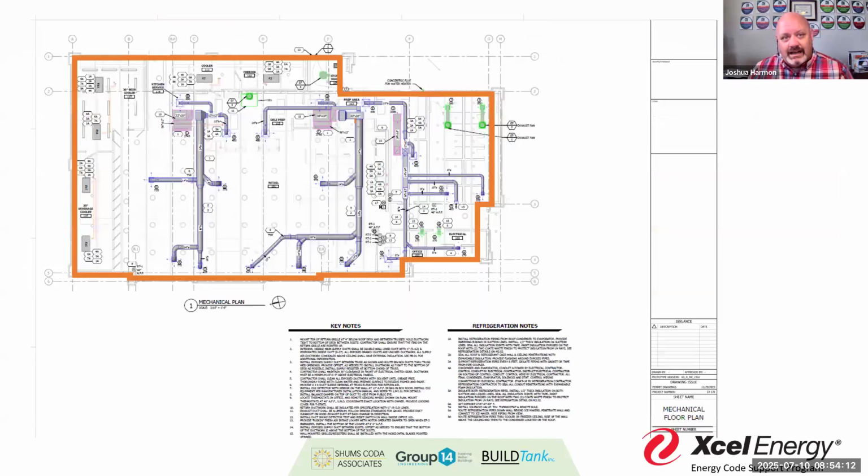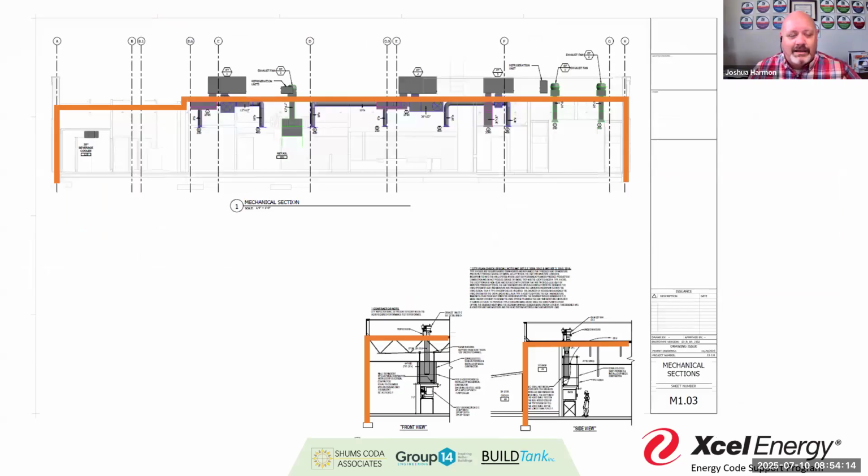And again, those duct designs, I need to see that duct design. I don't know how many times I have to tell them I need to see the ducts. And not only do I want to see the ducts, but I want to make sure my inspector, when he's on site, depending on that design, has a diagram, a detail sheet that says what each termination, each elbow, each discharge is going to look like.